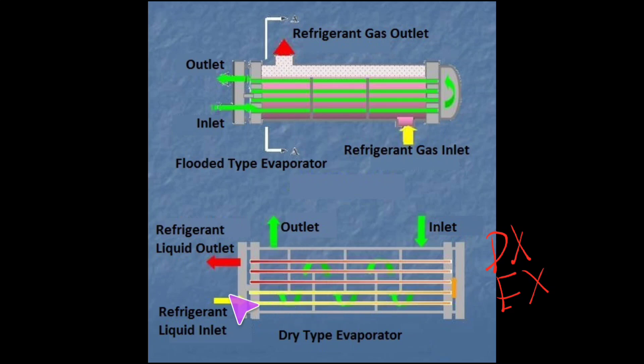So you'll have a little metering device here. It'll be inputting and monitoring superheat here, and that's how it's running. Most of the time, these flooded designs where the refrigerant is outside of the tubes can typically maintain less than three degrees of approach.